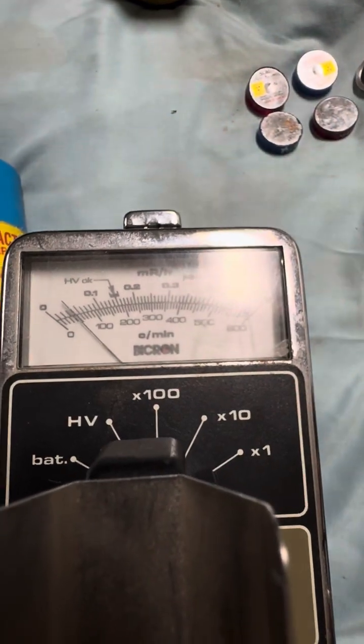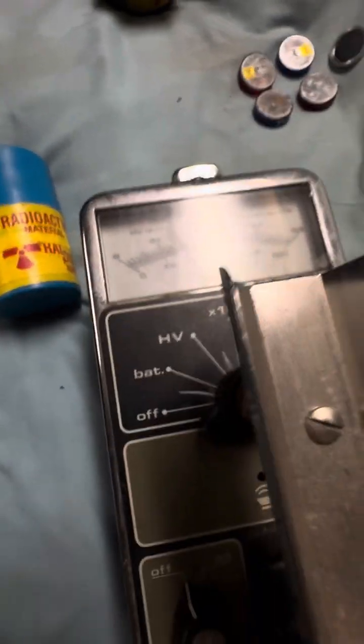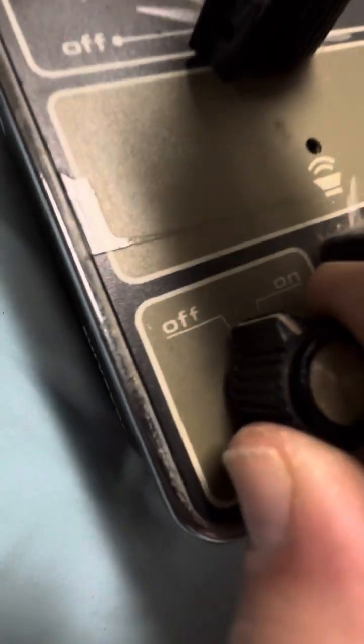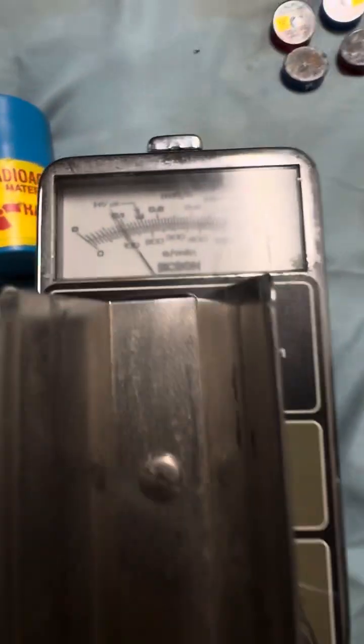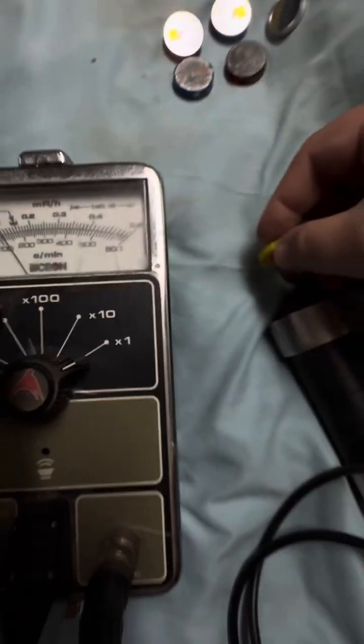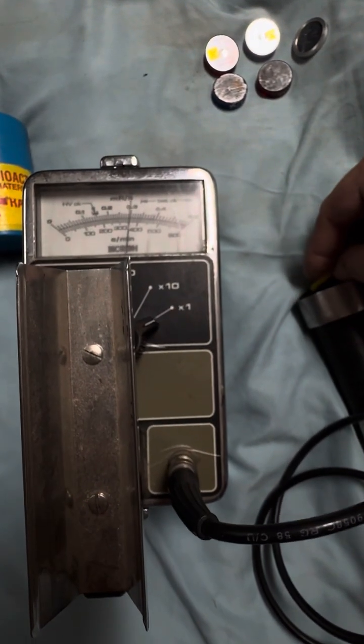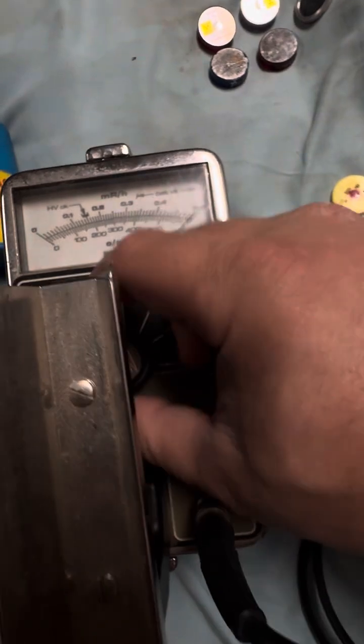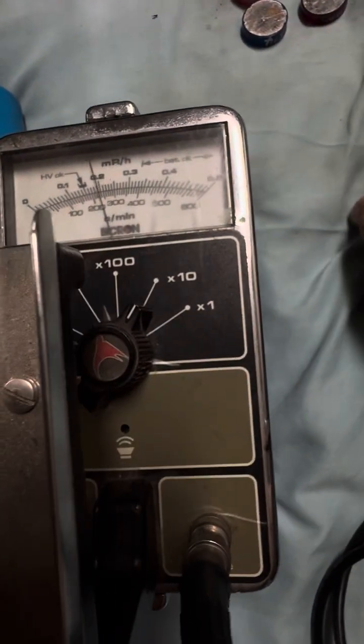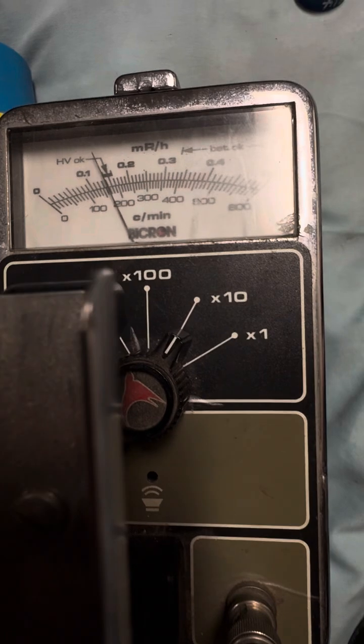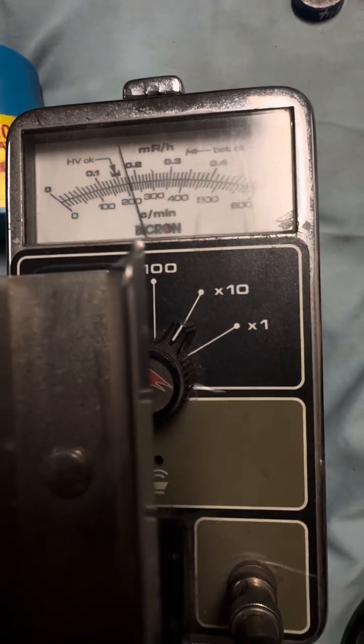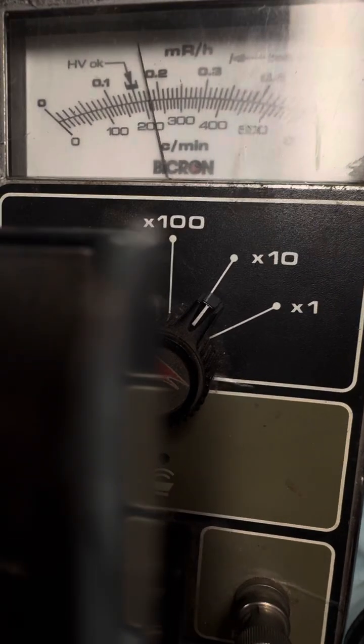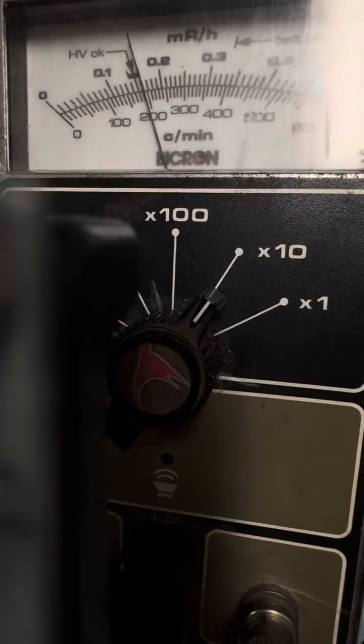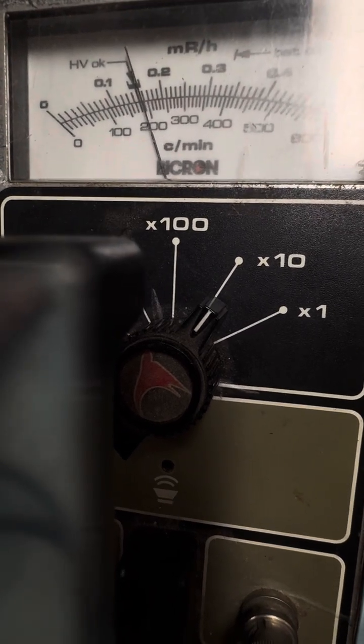So first we have a Cesium 137 source. And I'm going to turn on the sound with the sound switch so you can hear the count. And let's put this up to the probe. And that completely maxes out the X1 scale. So let's go up to X10. That's a little better. Now, this isn't reflecting true dose in milliroentgens per hour because it's an alpha, beta, gamma probe. And it doesn't accurately reflect.